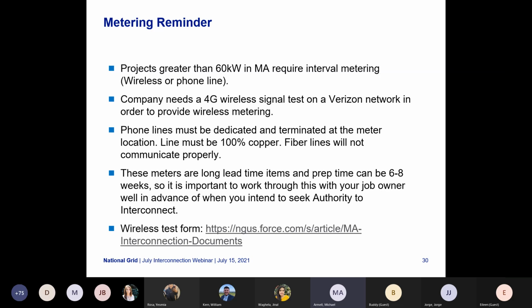These meters are long lead time items, and prep time can be 6 to 8 weeks. At a minimum, you should give us probably 2 to 3 months lead time in order to get these programmed and then out to the field prior to seeking the ATI on this. This is the link for the wireless test form. And again, it's a one-pager with a screenshot off of the phone to just determine the signal strength in that area. Okay, next slide.